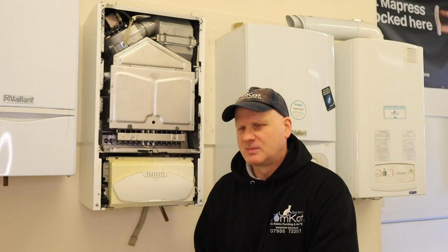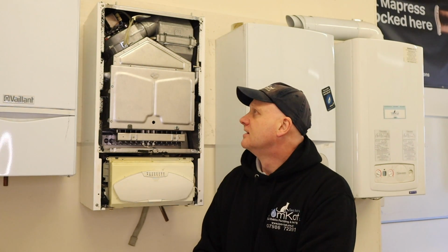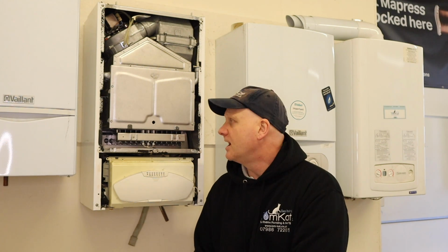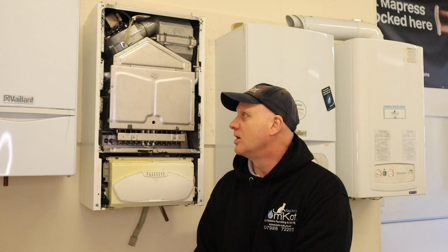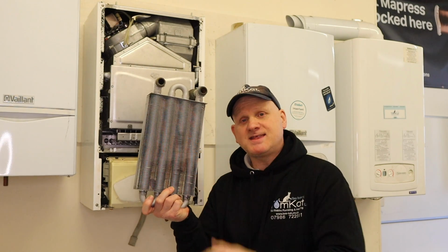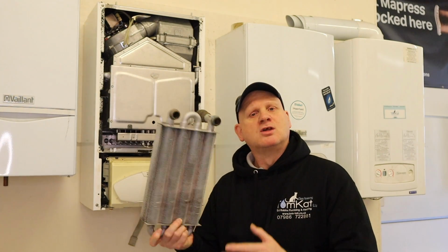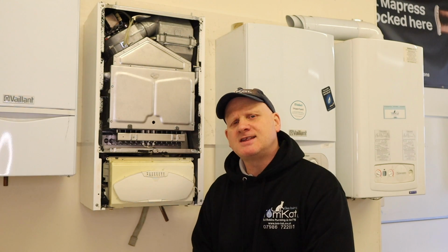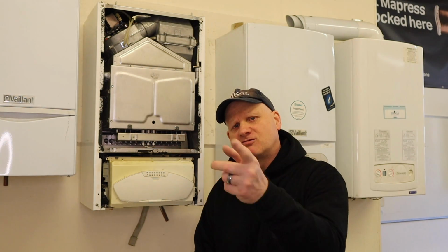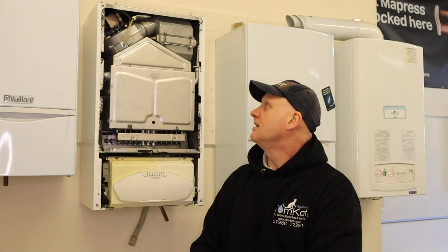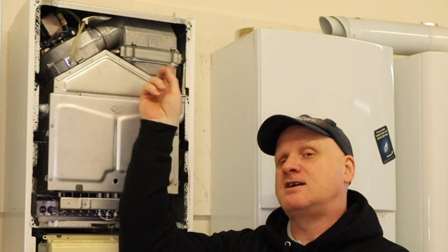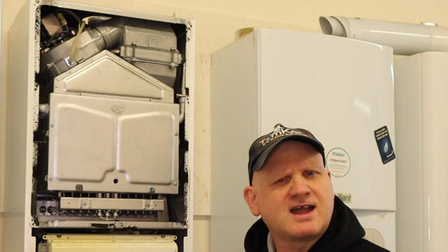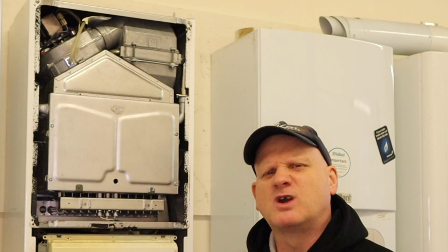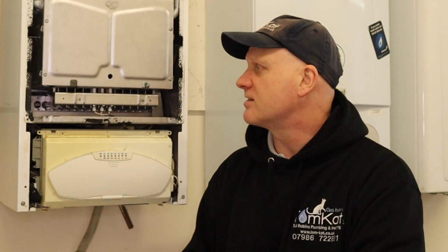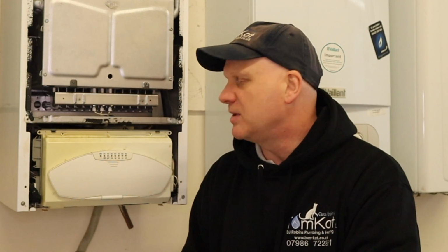It still rots them. Now, the boiler we've got here is a Heatline Band B condensing boiler. It has the same main heat exchanger as this one. So why are we still calling it a condensing boiler if it's got a copper heat exchanger? And I've just told you it rots. Well, we have this heat exchanger here, which is a secondary one, pretty much like I explained with the cast iron heat exchanger, where they're using a stainless steel secondary heat exchanger to take out more heat from the flue gases. And this is exactly what this Band B boiler did.